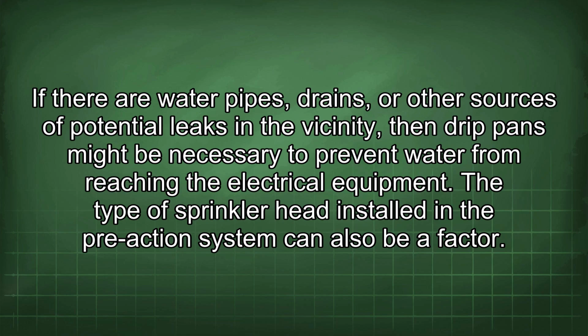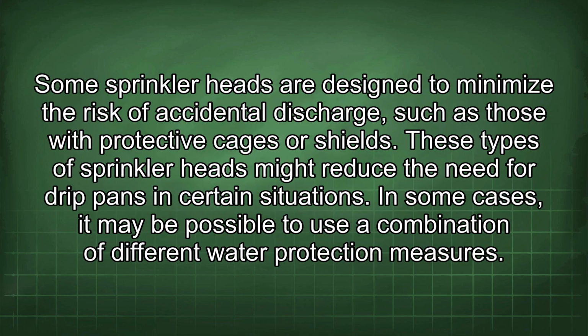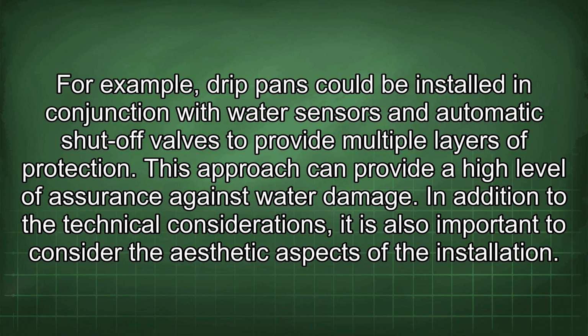The type of sprinkler head installed in the pre-action system can also be a factor. Some sprinkler heads are designed to minimize the risk of accidental discharge, such as those with protective cages or shields. These types of sprinkler heads might reduce the need for drip pans in certain situations. In some cases, it may be possible to use a combination of different water protection measures. For example, drip pans could be installed in conjunction with water sensors and automatic shut-off valves to provide multiple layers of protection. This approach can provide a high level of assurance against water damage.